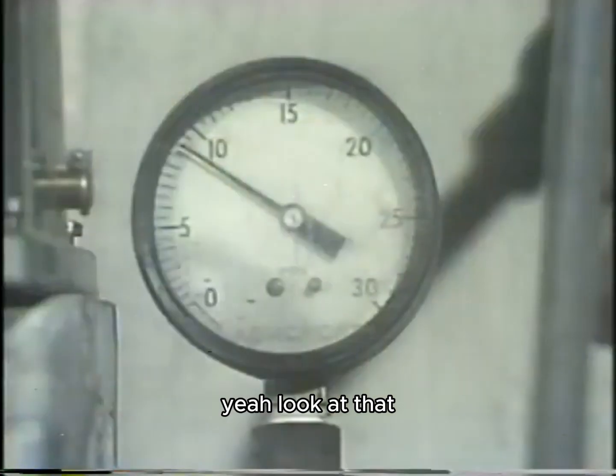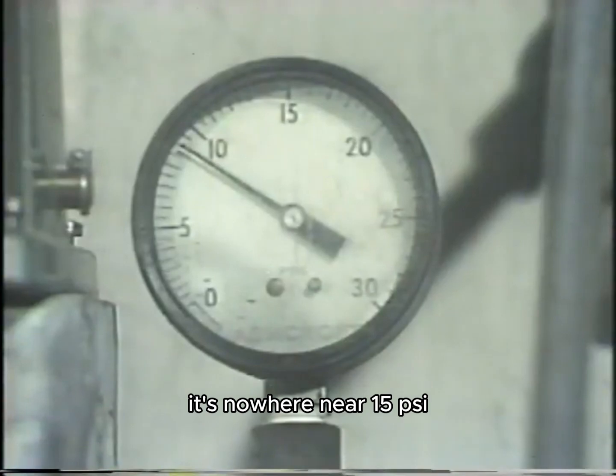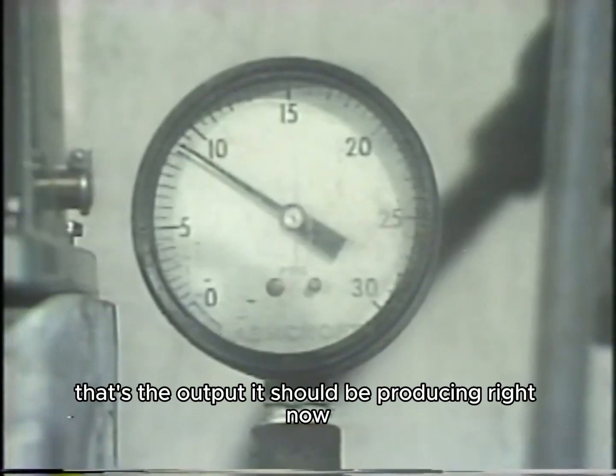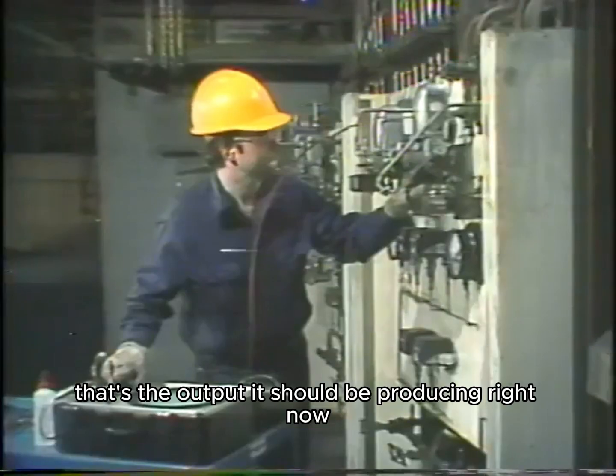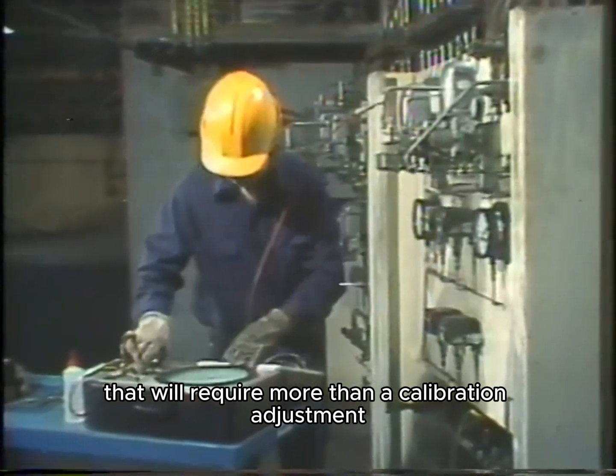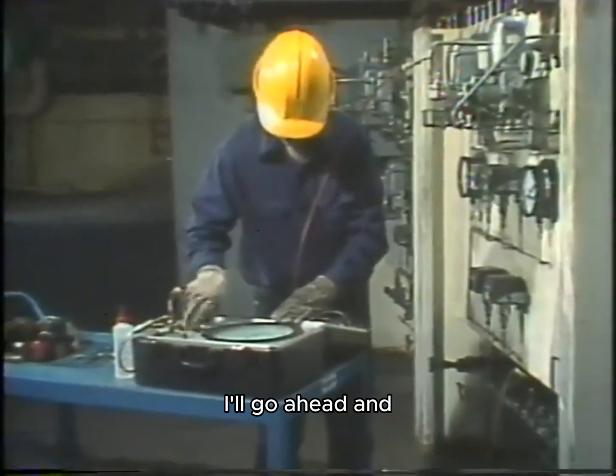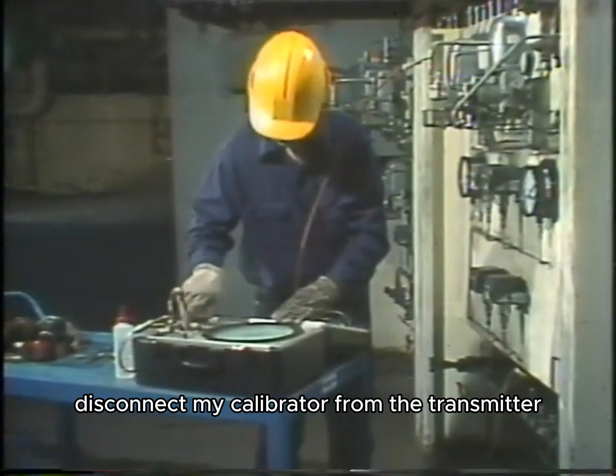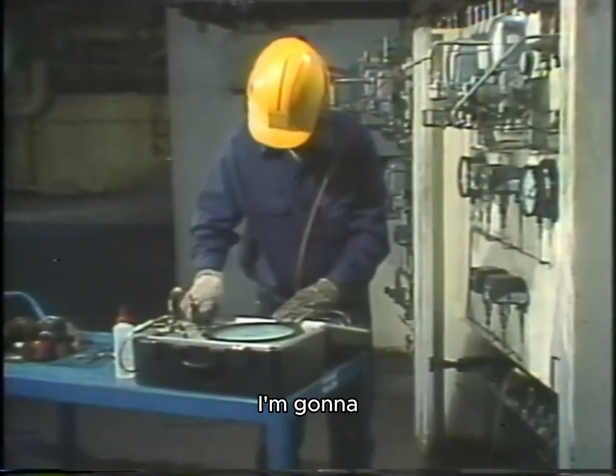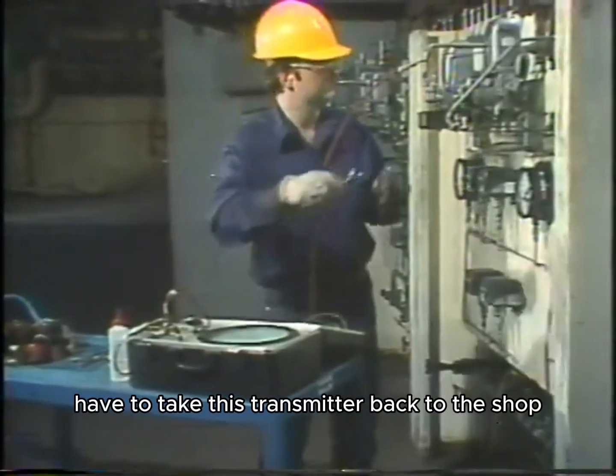Yeah, look at that. It's nowhere near 15 psi. That's the output it should be producing right now. That'll require more than a calibration adjustment. I'll go ahead and disconnect my calibrator from the transmitter. I'm going to have to take this transmitter back to the shop. There's definitely something wrong in here.